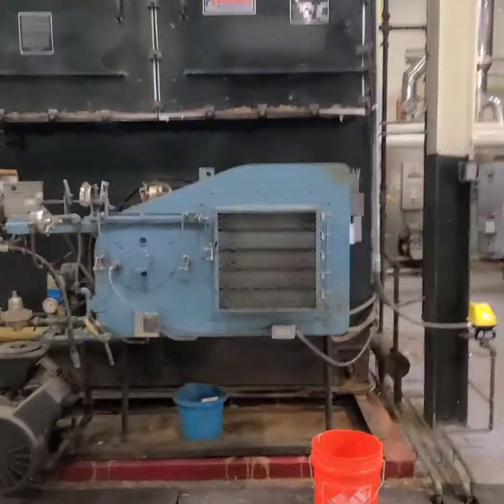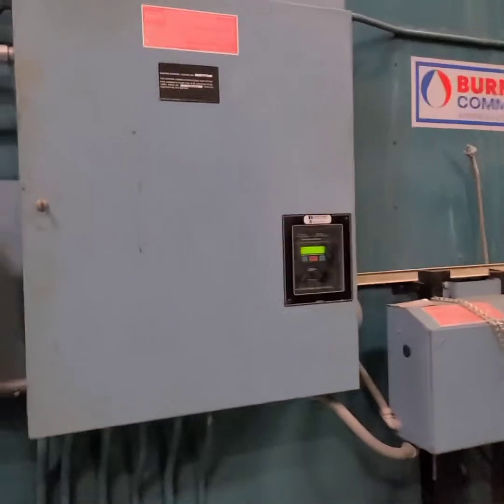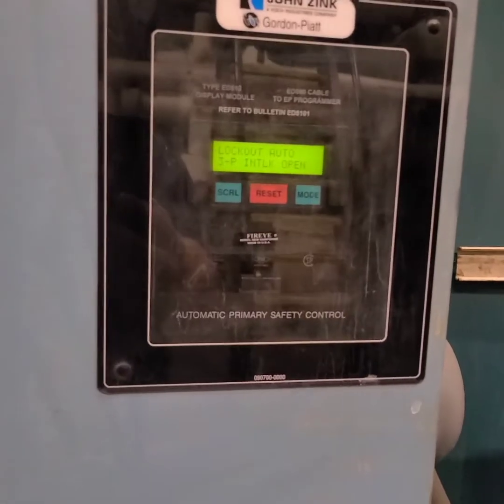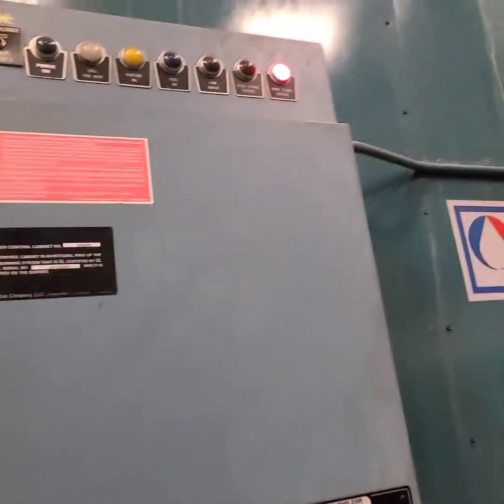I wanted to make a video today on an old Burnham commercial boiler with a Gordon-Platt dual fuel. It came in for a main flame failure / 3p interlock problem. The main flame failure signal will confuse a lot of people, especially the facility engineers.